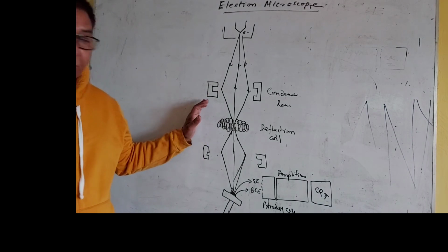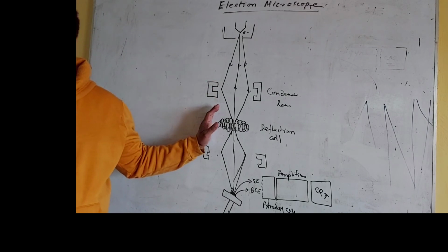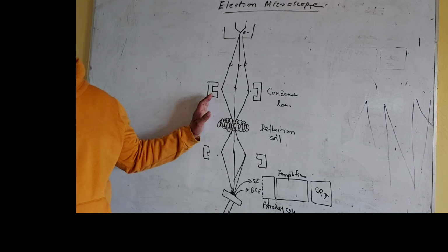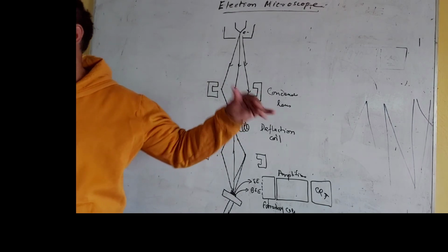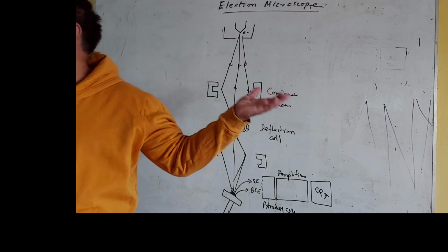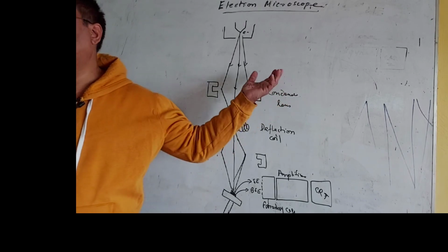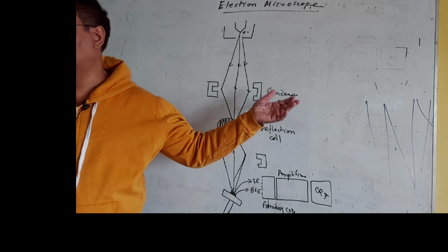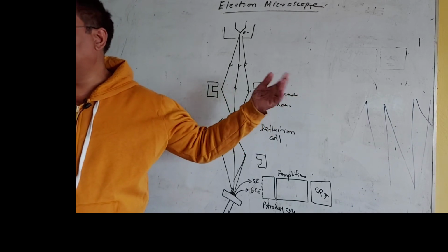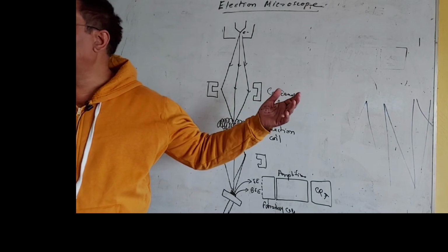These are the two main differences on the basis of instrumentation. And principle-wise, the wavelength of the electron beam here is very, very less compared to the light you are using in light microscope. The limitation of that is 400 nanometer. Here you can go up to 10 angstrom or even lesser than that theoretically, but practically you have to keep it at maybe 10, 25 nanometers.